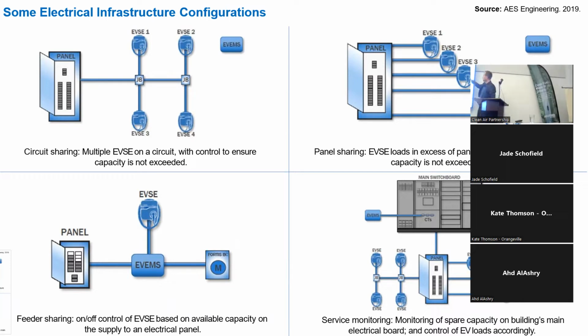You can also do panel sharing, where all the sharing occurs at the panel level. In single-family homes or townhomes, you sometimes do a feeder sharing arrangement, where your meter feeds into your residential panel, and there's monitoring on that feed that says, there's capacity on that feed, like there is the vast majority of the time, so we can allocate charge to your EV charger.